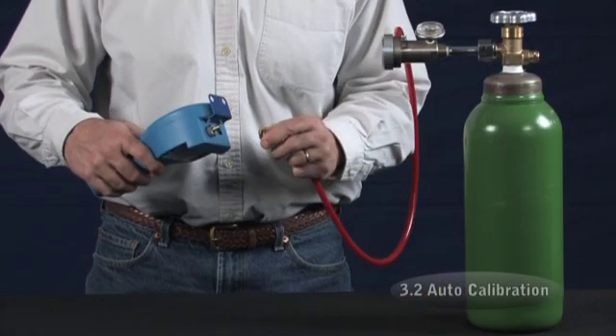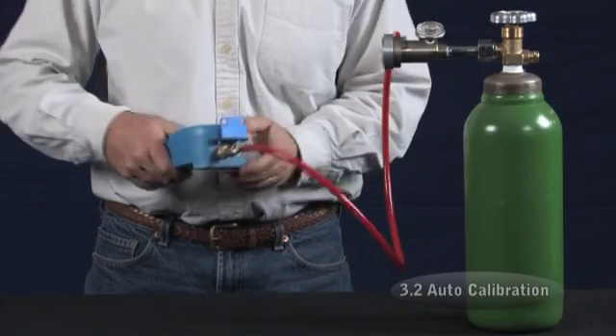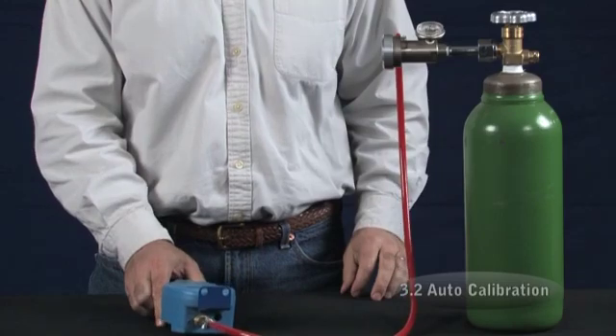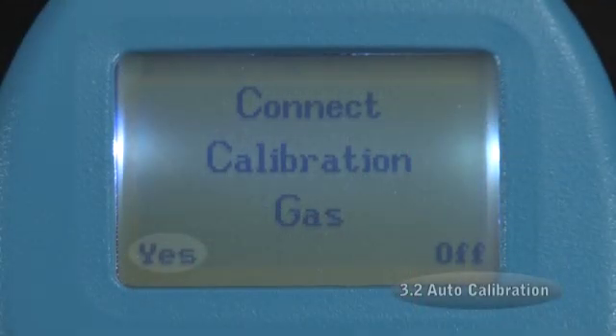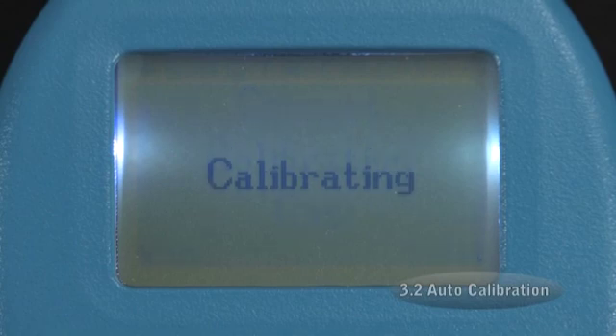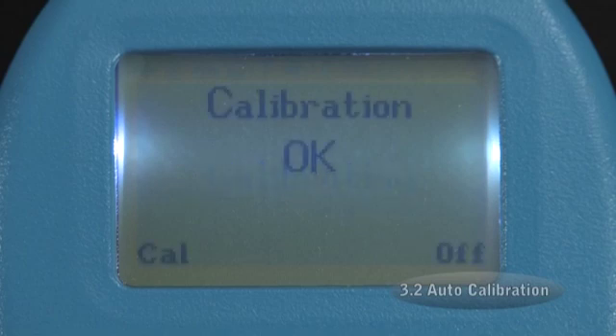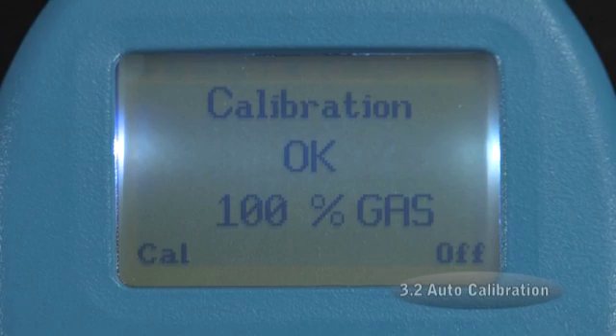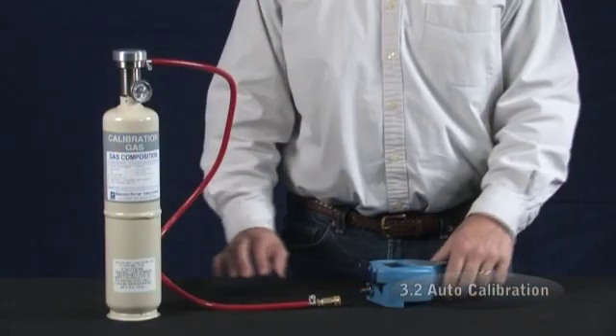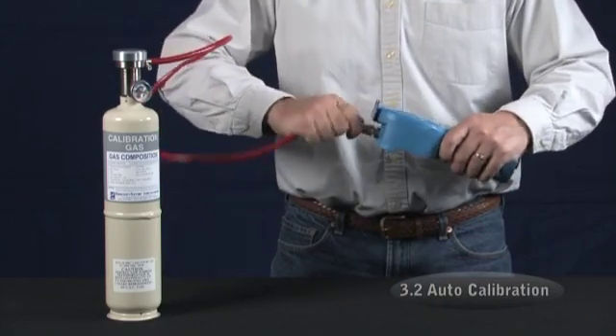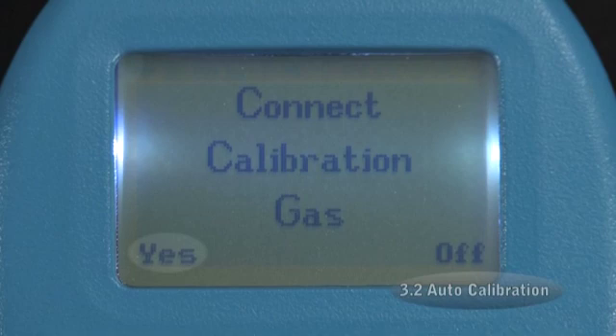Attach the Explorer to your source of gas. If you are not using a demand regulator, make sure that the valve is turned on and press the left button under the word Yes. The Explorer will display the word Calibrating while the sensors are being calibrated. When finished, the display will show Calibration OK and reveal confirmation readings for the gas used to calibrate, in this case 100% gas. Now, to calibrate with CalGas, disconnect the 100% methane or system gas, then press the left button under the word Cal. Connect the CO methane CalGas, and press the left button marked Yes to run the calibration.